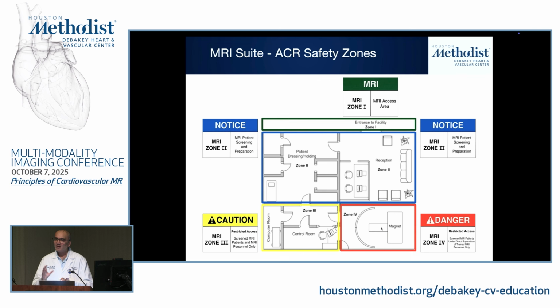So if you take anything that's magnetic, it's going to get deactivated inside there. So from a safety standpoint, like a stethoscope, you would not want to take into that room. Don't take anything that's ferromagnetic that'll get pulled by the magnetic field, but also anything that has a magnetic stripe will get deactivated, okay? So that's zone 4. You should not go into zone 4 unless you're invited to go into zone 4. Zone 3 is the area that's directly outside of zone 4.